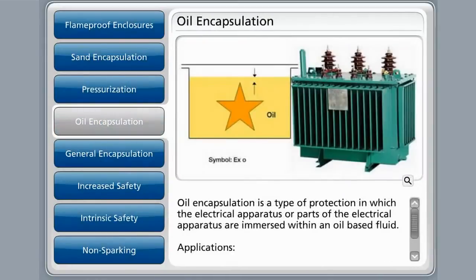Oil encapsulation is a type of protection in which the electrical apparatus, or part of it, is immersed within an oil-based fluid. The general application for this type of protection would be used for switchgear units, circuit breakers, and transformers.